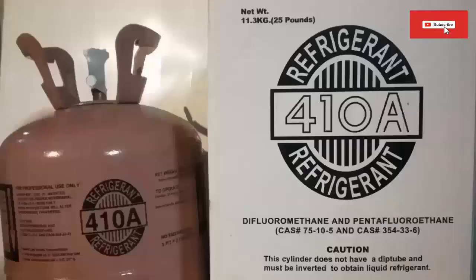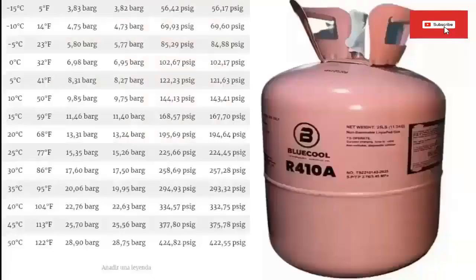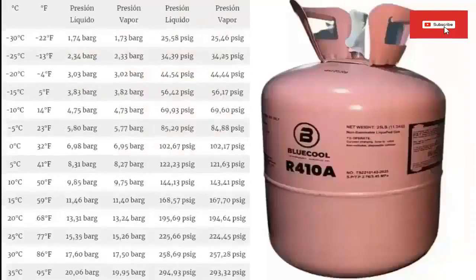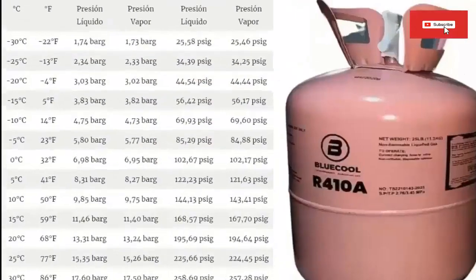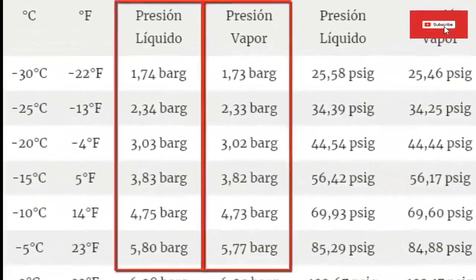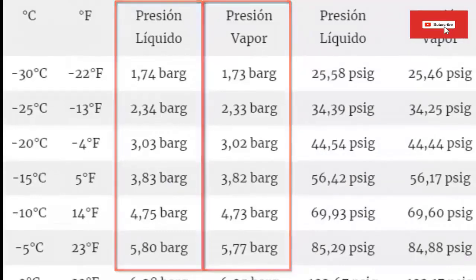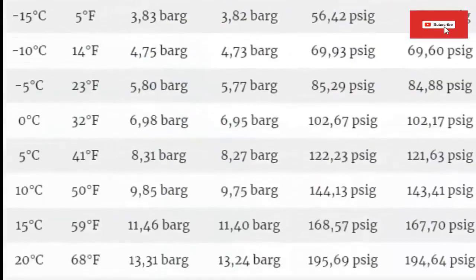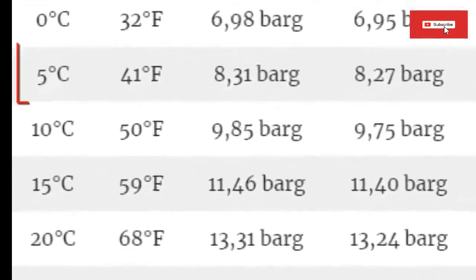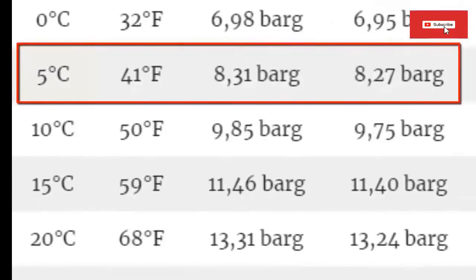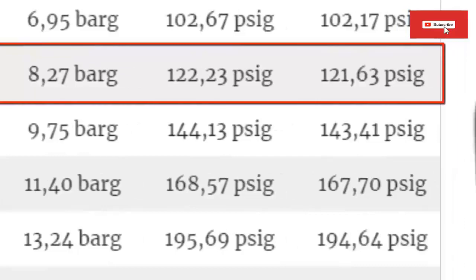On the screen we have the pressure-temperature table of refrigerant gas R410A. Although the table shows two pressures — one for liquid and the other for vapor — since the glide of this gas is very low, the difference between both pressure values is negligible. In this case, we are going to work with the vapor pressure. For an evaporator temperature of 5°C (41°F), typical of an air conditioner, the gauge pressure at this point is required to be 8.27 bar (121.63 psi).